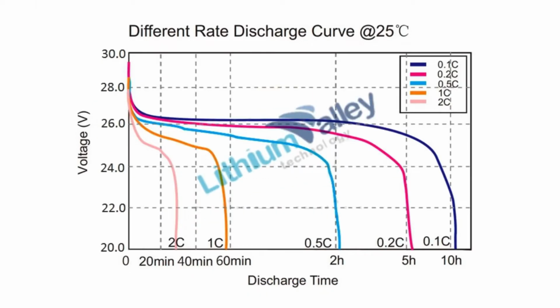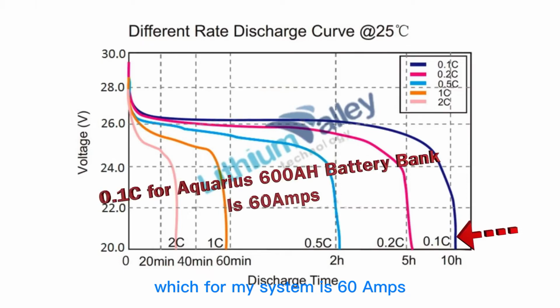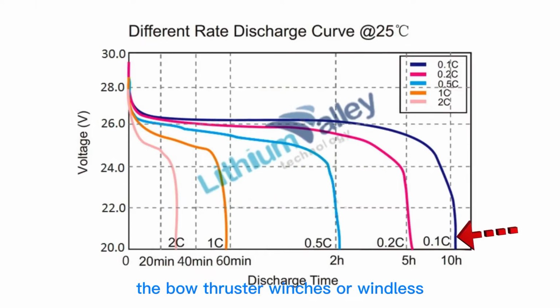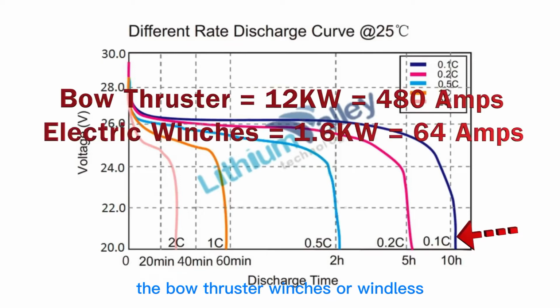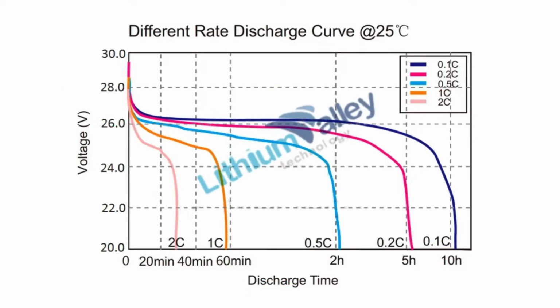I'm really not sure about the cutoff voltage at the low end, 20 volts. I believe that's actually 24. As mentioned earlier, I want to keep my discharge rate or discharge current below 0.1 C, which for my system is 60 amps. Except for when I use the bow thruster, winches, or windlass, I expect to be well below this self-imposed limit of 60 amps.